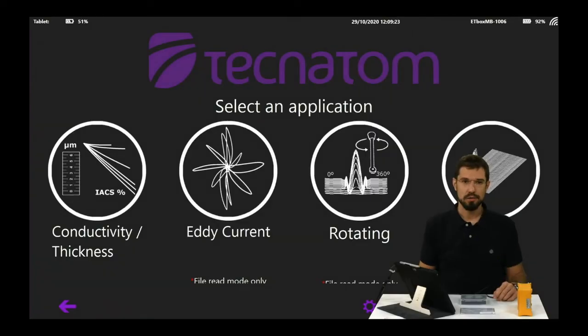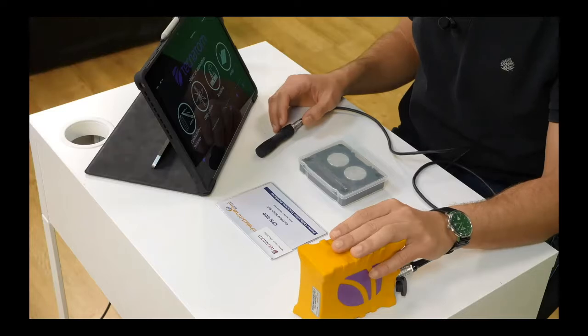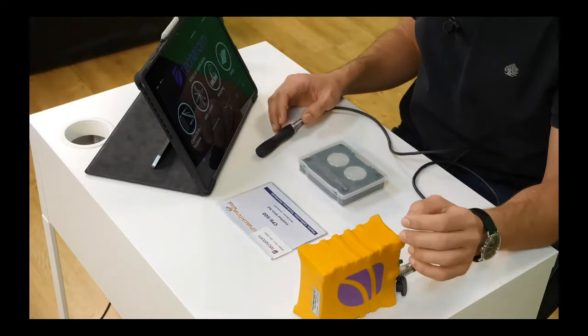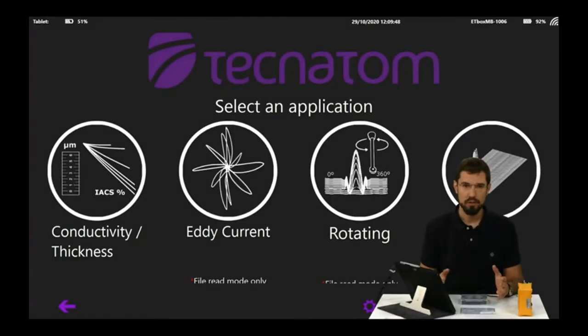In applications for industries such as aeronautics, the need to measure conductivity changes is very common, for example, changes produced by overheating on the brakes over the wheels. Similarly, the thickness of paint layers or coatings with non-conductive materials on metallic components is also measured. The ETboxMB equipment allows these measurements independently or together, in different working modes.